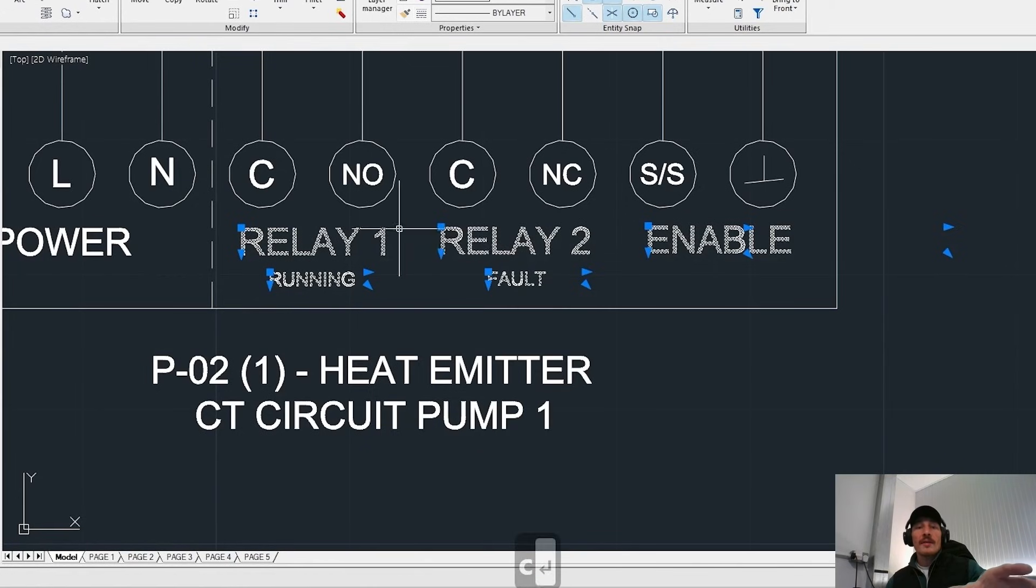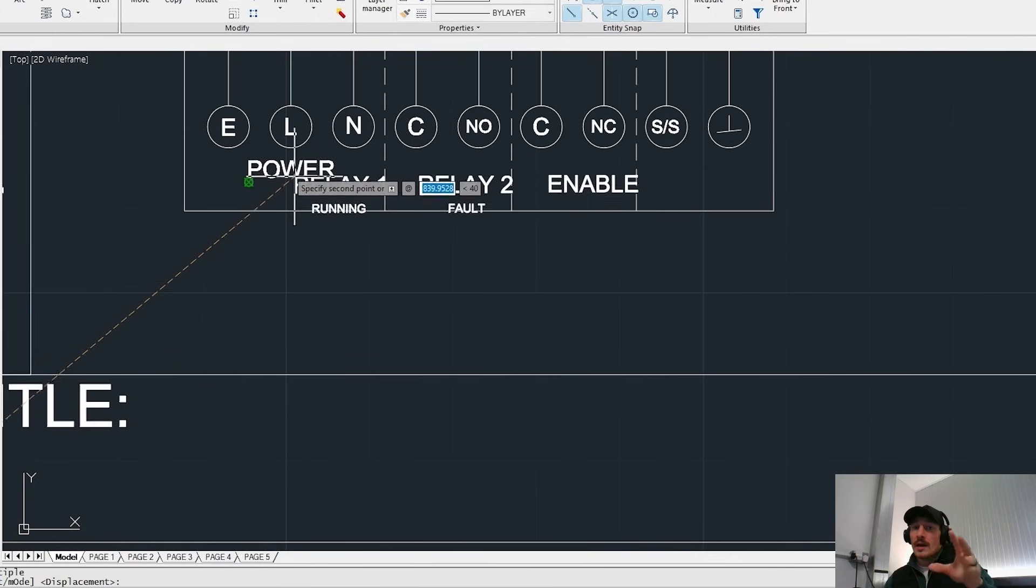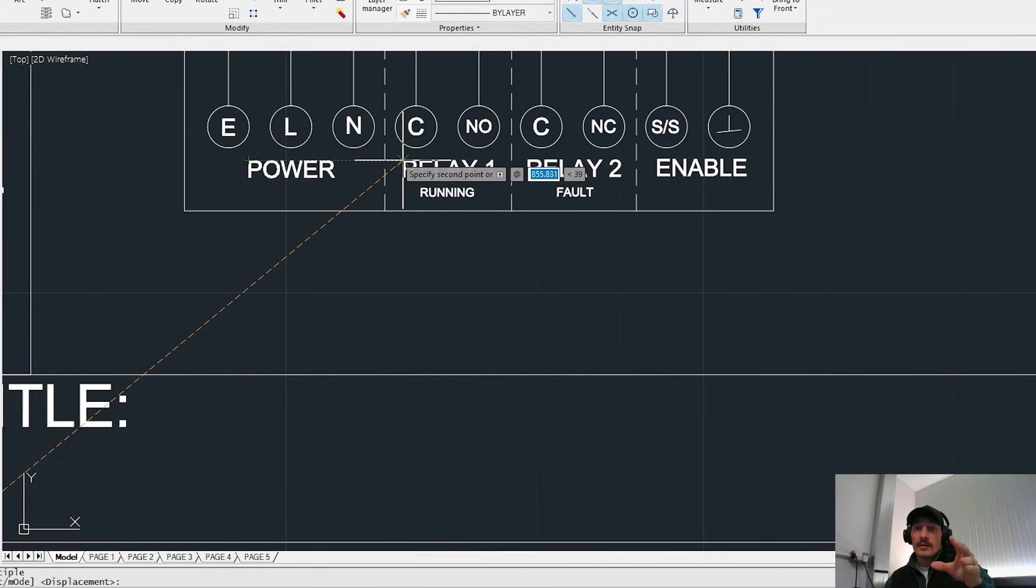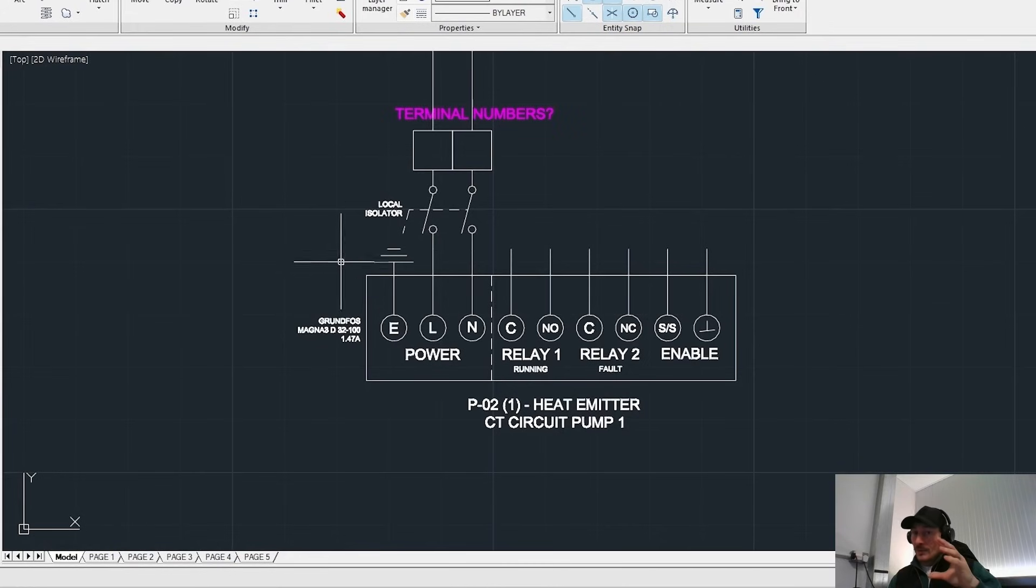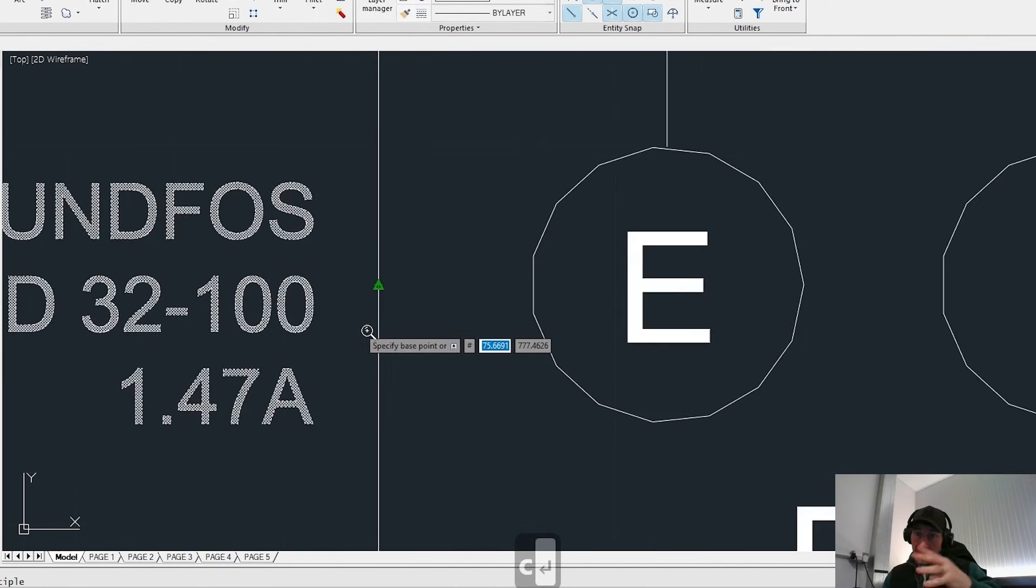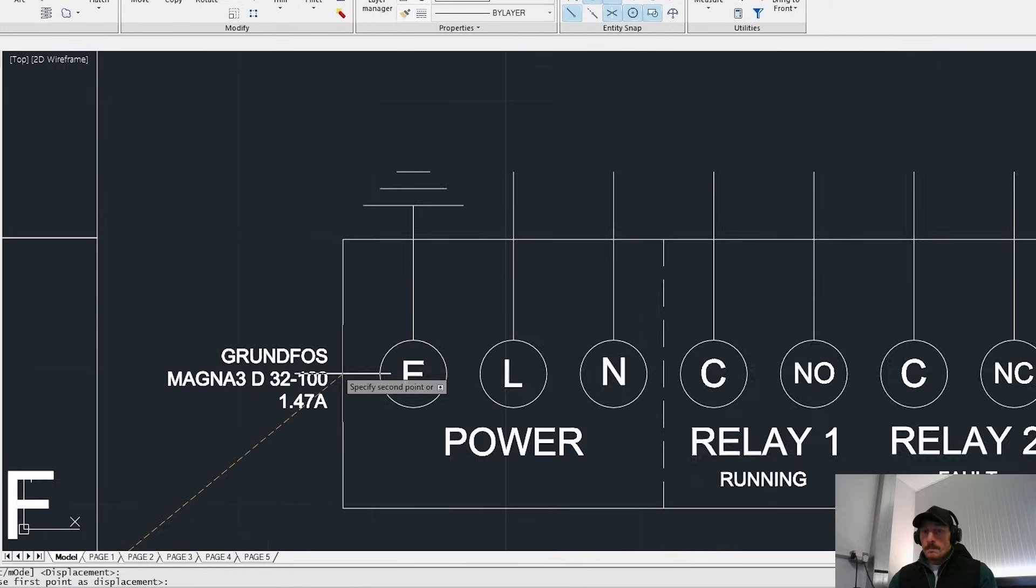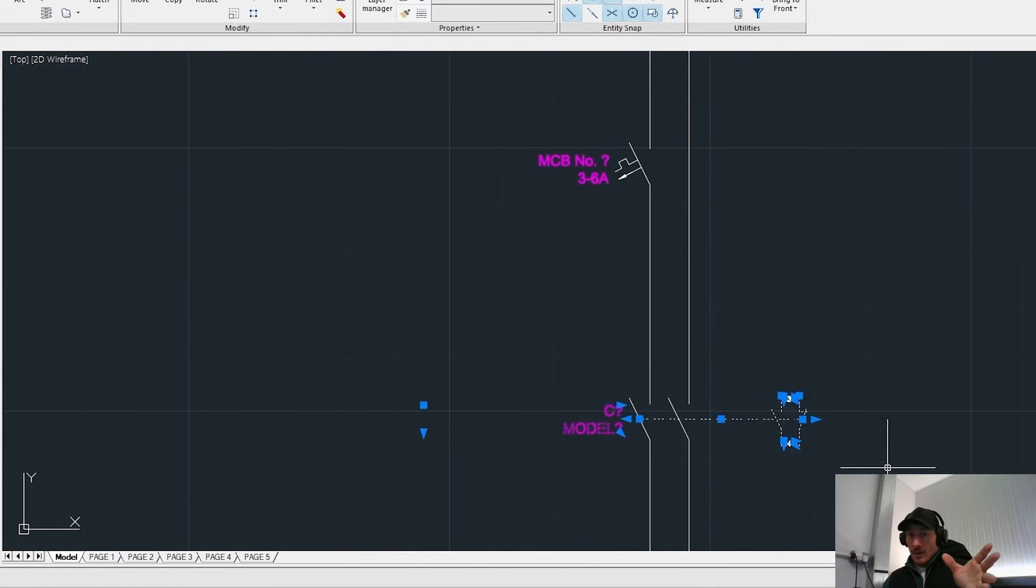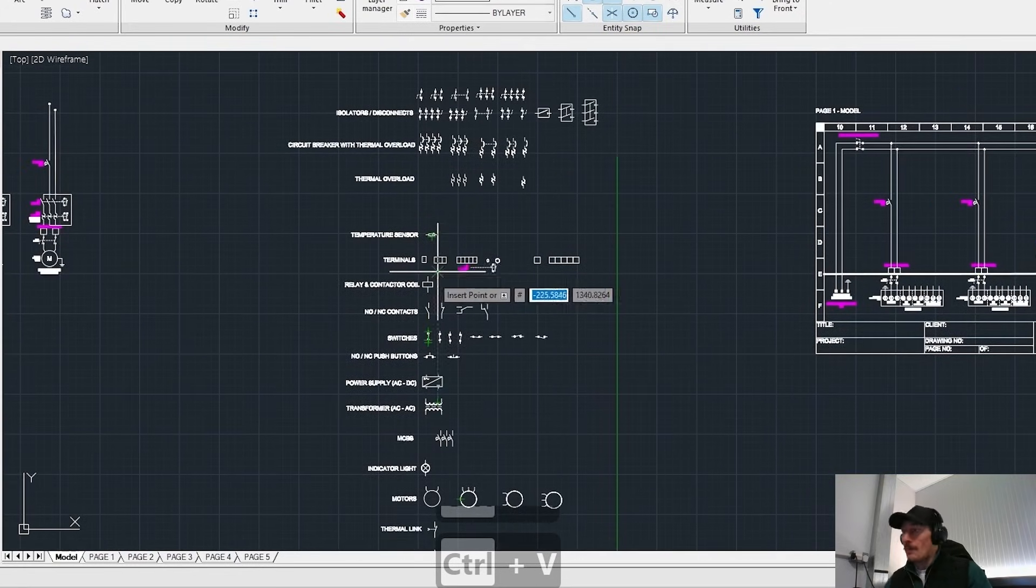But you can see here that what we're doing is the run output on relay one. You've got two relay outputs on these smart pumps, one to tell us whether the pump is running that feeds back into the BMS or the control system and one to let us know if the pumps gone into fault. So C is the common and the NO is normally open and the NC is normally closed relay connections on that pump.